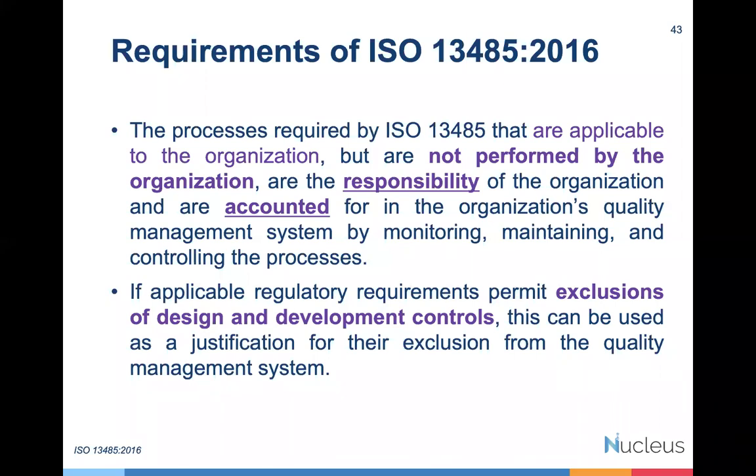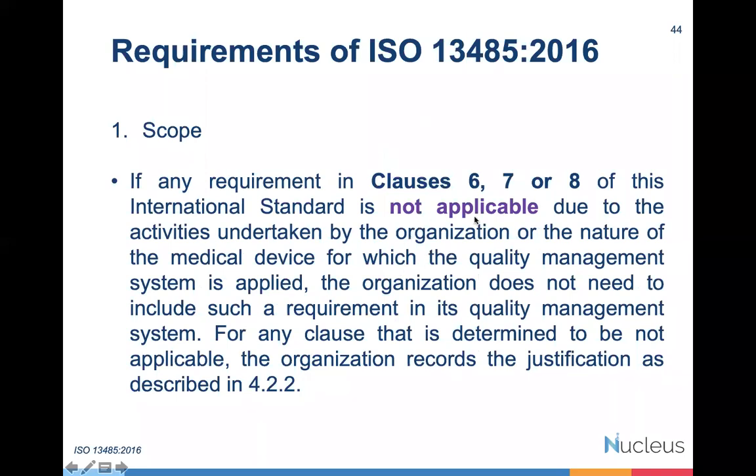And in this standard, unless otherwise specified by the regulatory authorities, you are free to exclude the design and development. That is clause number 7.3. That is the only clause we can exclude, if your regulator allows that. Otherwise, all the requirements are applicable to you. We cannot exclude, but they are also giving a provision for non-applicable clauses.